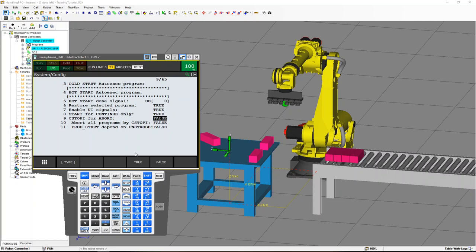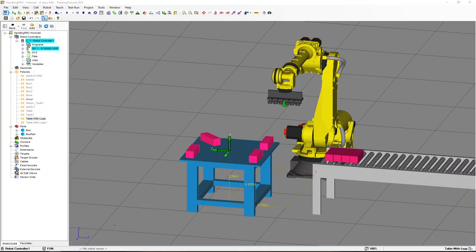By nature, if you are running the robot and someone issues an e-stop, you will see at the top here, instead of the word abort, it will say your program is paused at line something. So when it's paused, all you have to do is give the robot the start signal again. That can come from the controller or from a PLC or from a push button. But if you tell it to start again, it'll simply take off from where it left off. So it's definitely a strategy thing. You're more than welcome to start from the beginning if you want, but you don't have to.